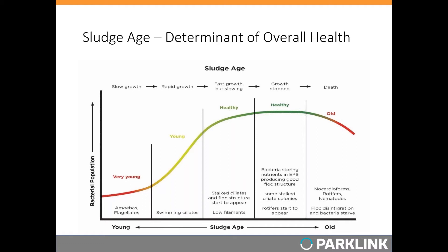If your sludge age is too young, you have more BOD than your bacteria can remove in a good time frame, meaning nitrifiers can't get enough oxygen to oxidize ammonia. Floc formers will use up all the oxygen and they compete better for oxygen than nitrifiers. If sludge age is too old, you may see poor BOD removal or disintegration and breakup of the floc as bacteria inside it die, and filamentous bacteria growth may also contribute to floc breakup.